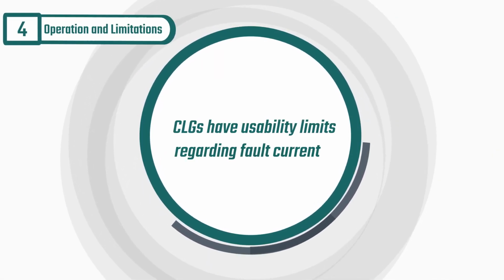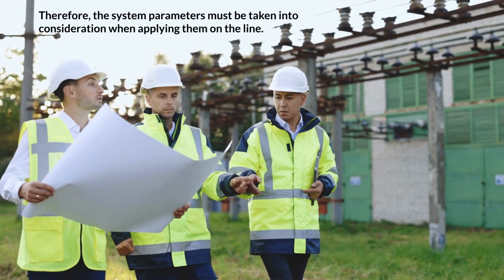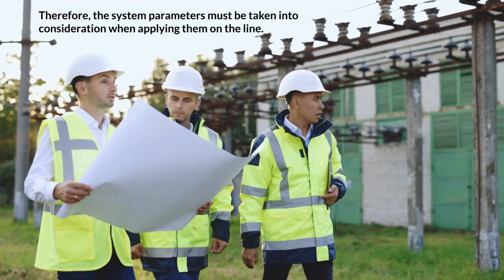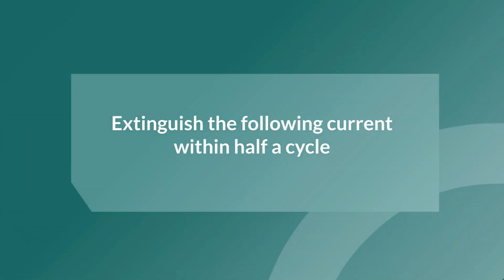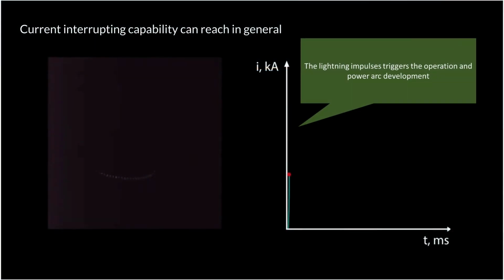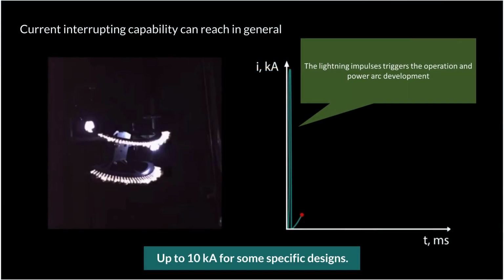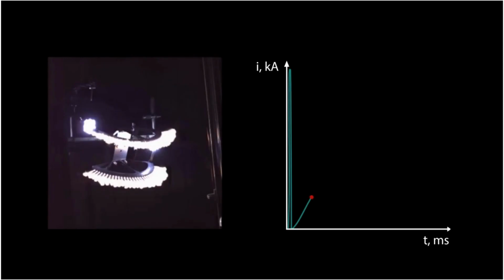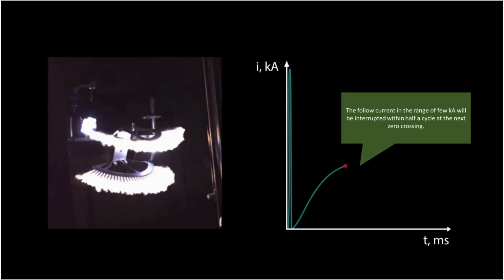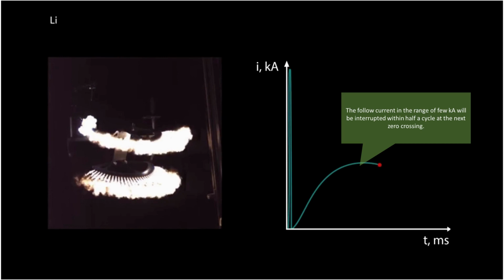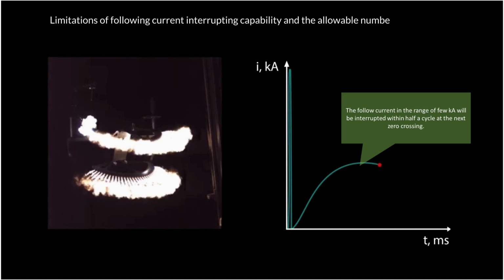Operations and limitations. It should be noted that CLGs have usability limits regarding fault currents. Therefore, the system parameters must be taken into consideration when applying them on the line. All CLGs are certified to extinguish the following current within half a cycle. The following current interruption prevents the breaker operation and the subsequent lightning-induced outage. The current interrupting capability can reach in general up to 10 kA for some specific designs. However, large energy dissipation can be expected at interrupting the power arc in the active part, which gives limitations of following current interrupting capability and the allowable numbers of operations.